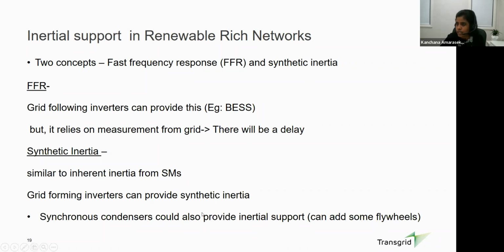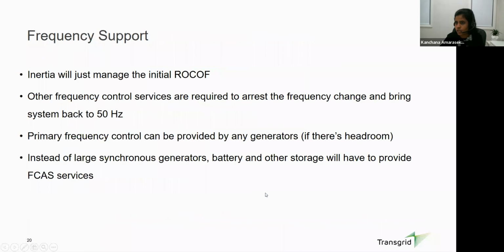And the third concept is synchronous condensers. As I mentioned, synchronous condensers can provide system strength services as well. They can also provide inertial support, and we can add some flywheels too. The next network support service I wanted to discuss is frequency support. As I mentioned, inertia will manage the initial rate of change of frequency during a frequency disturbance, but other frequency control services will help arrest that frequency change and bring the system back to 50 Hertz.